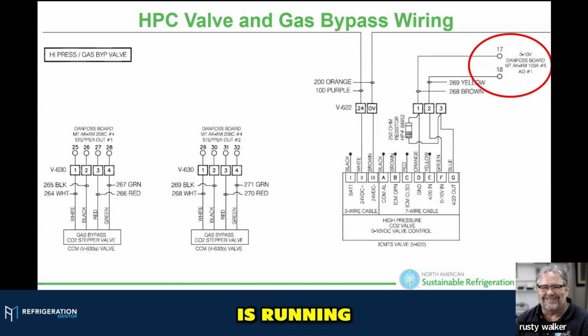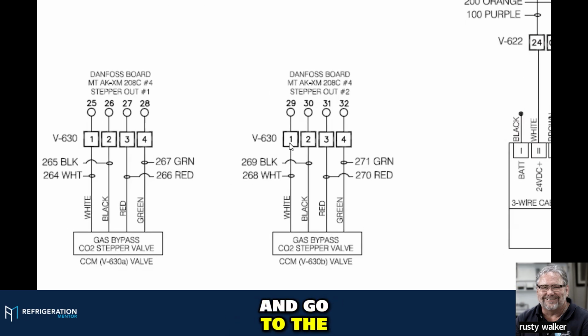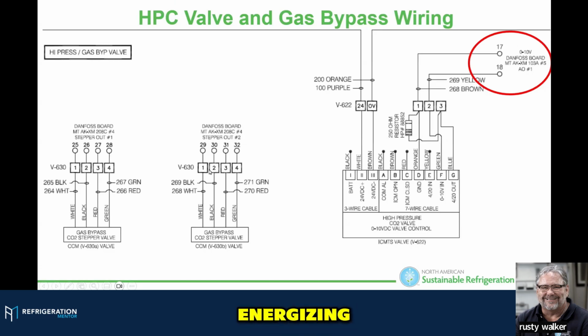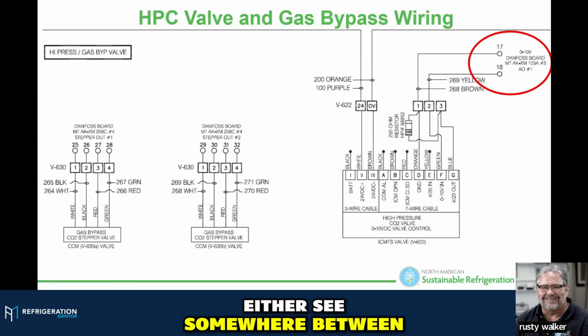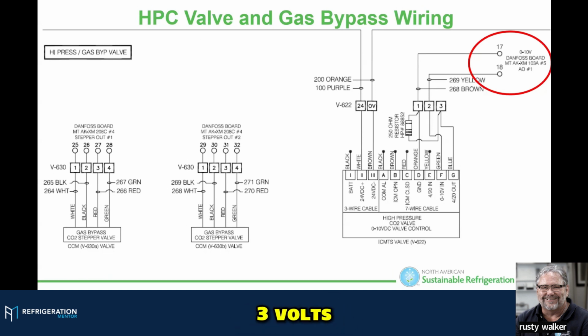But if the rack is running and you don't know if it's the Dixell, the 326, whatever - you can take your meter, put it on DC, take your leads and go to the white and black wire. We're all using white, black, red, and green, that's just the standard. I put my meter here. If the valve is energizing and working properly, and my controller is sending the proper signal, I'm going to see somewhere between -5 and -3 volts DC.